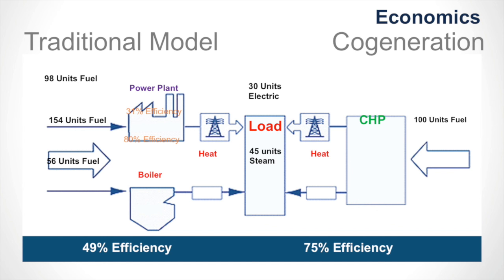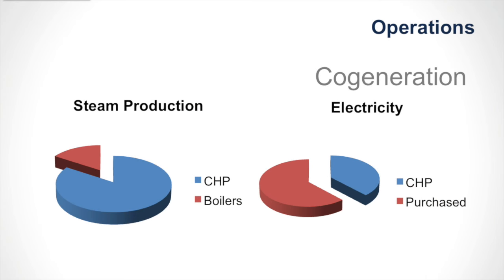And that's how a cogeneration unit like ours saved us $2.5 million a year. So this is what it looks like in our loads. Our cogeneration unit produces about 80% of our steam annually and about 40% of our electricity. We wish it was more here in electricity, because electricity is more expensive than gas. However, if we didn't use it all, we'd be no better than the utility. So you size these things based on your heat load, on what your steam load is in the summer, in essence - because otherwise, you'd be venting exhaust and throwing it away like the utility does.